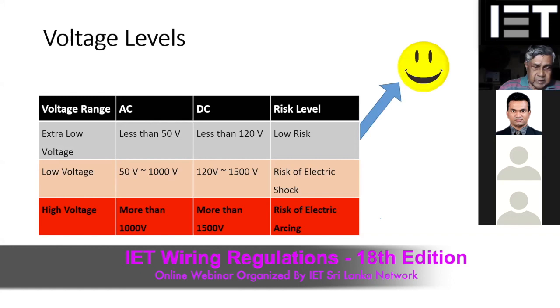Within the extra low voltage, there are special voltage categories as well, such as less than 12 volts or less than 30 volts, especially for bathrooms, swimming pools, sauna heater locations, those types of locations. There are special requirements that you have to use extra low voltage, but even lower than these voltages. As I said, there are subcategories, but we categorize them as extra low voltage if the voltage is less than 50 volts AC. Then we have the low voltages, which is 50 volts to 1000 volts. If you are exposed to that type of voltage, there is a risk of electric shock: a current will flow through the body, and if that current is sufficient and you are exposed for a sufficient time period, then that person can get an electric shock.